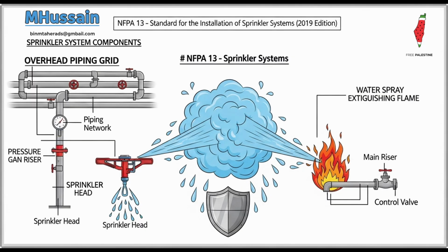In this section, let's move from the systems infrastructure, the pipes and water, to the nozzles themselves, the business end of fire protection. We really have to start with K factors, which quantify discharge capacity. Yeah, K factors are fundamental. They define how much water flows out of a sprinkler head at a given pressure. Simply put, the higher the K factor, the greater the flow capacity of that head.